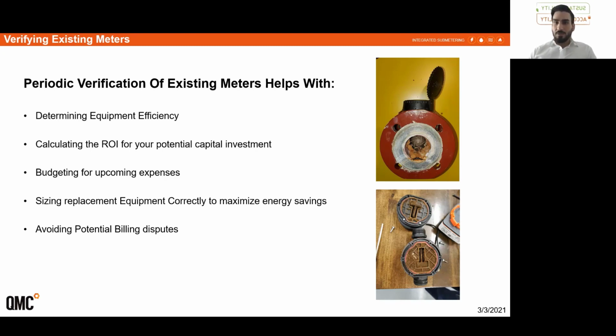So meters with moving parts, we usually recommend biannual, every other year, to be verified by the property. Same thing with thermal meters, if they're using measurement principles with no moving parts, so no impellers, such as mag meters and ultrasonic meters, those require a less rigorous maintenance regime. So those are usually maintained and verified every 5 to 10 years, versus meters with moving parts, which, depending on the load, need to be verified every year or every other year. So it really depends on the type of technology used for that particular meter, and also the site conditions.